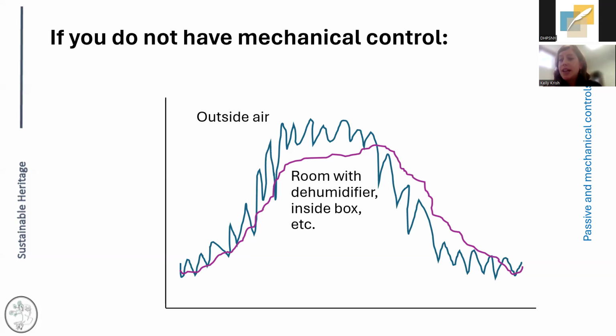As well, oftentimes people will monitor within storage enclosures, and this can be an effective way to see how much buffering you're getting from different types of boxes. I've seen institutions make decisions about the cost effectiveness of different enclosures by seeing how well they do at buffering against moisture changes compared to the cost. Because the more you invest in those passive means, the less you'd have to do mechanically. So even if you do have mechanical means of controlling your environment, I would still really encourage you to start by pulling up these data sets and looking at dew point and seeing what can be done to reduce the load on the mechanical system.